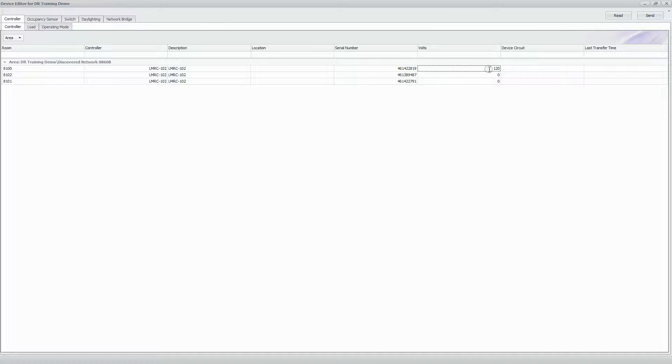Using the same process, we're going to go to the Controller tab and begin editing the room controller settings for load shed control. Best practice is to set the voltage parameters for all your controllers. In this case I'm connected to a 120-volt circuit, so I'll set it to 120, then Control+C, hold Shift and the Down arrow to select the column, and hit Control+V to paste the value — you can do this all the way down the row for a large number of room controllers.